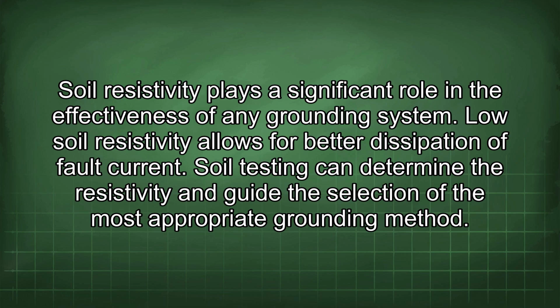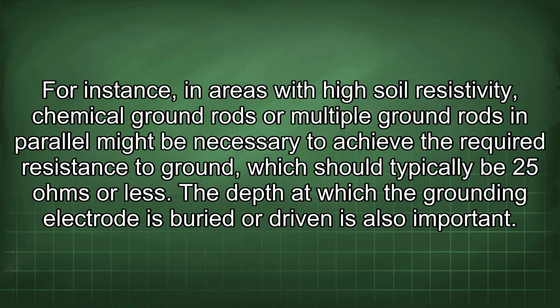Soil resistivity plays a significant role in the effectiveness of any grounding system. Low soil resistivity allows for better dissipation of fault current. Soil testing can determine the resistivity and guide the selection of the most appropriate grounding method. For instance, in areas with high soil resistivity, chemical ground rods or multiple ground rods in parallel might be necessary to achieve the required resistance to ground, which should typically be 25 ohms or less.